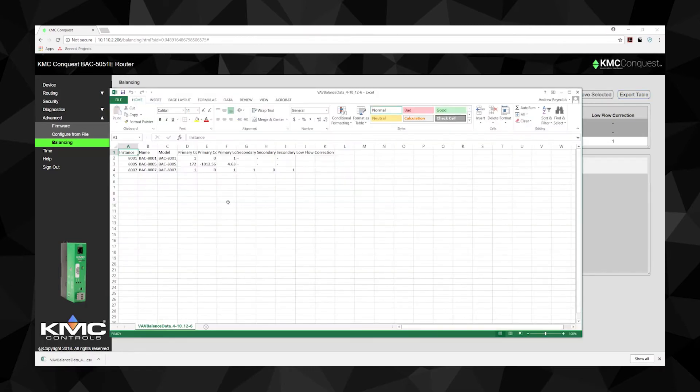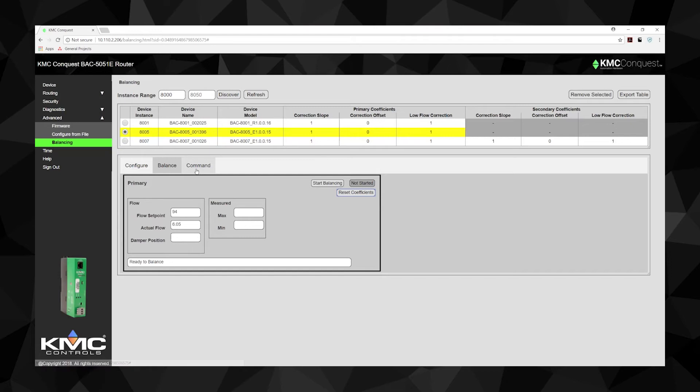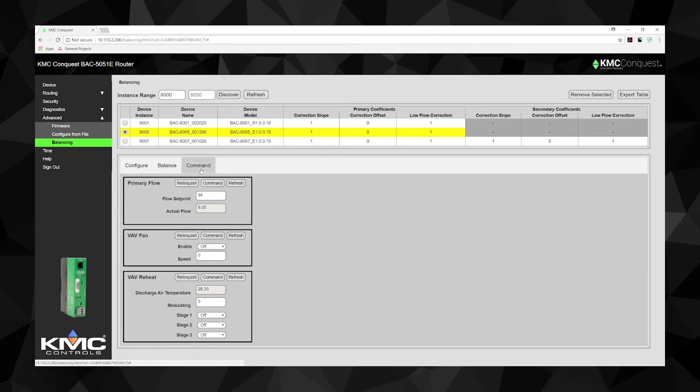You can use the router to command specific points related to device commissioning here on the Command tab. Here, manual airflow set points, as well as manual overrides of VAV fan and reheat outputs can be made. To write a point, enter your desired value and select Command.